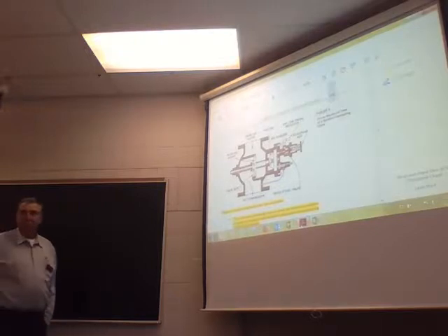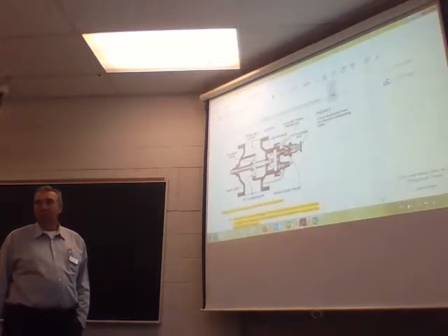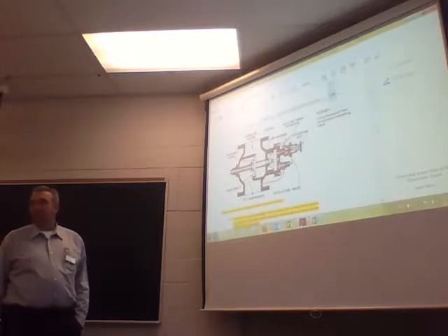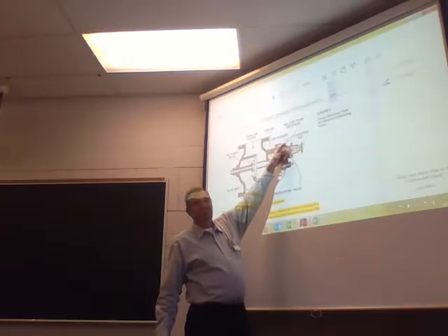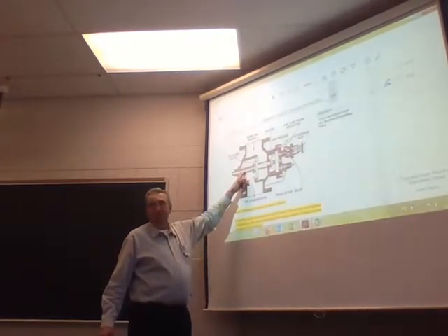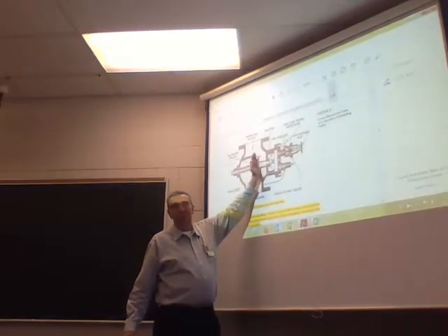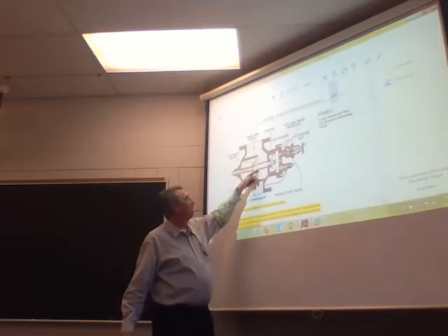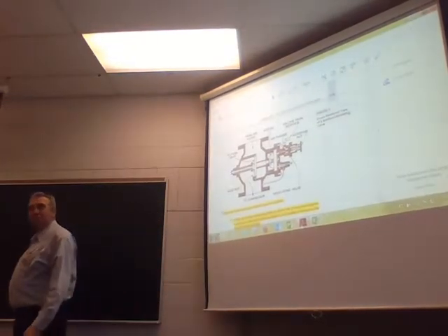So this is in the closed position. This is normally an open position. As it is right now, it's in the closed one, yes. When this pressure decreases, spring pressure overcomes the set pressure in my tank, pushes this open, just like a globe valve. We pull the globe back off. Now the air can go to my inlet valve, and we have compression all over again.